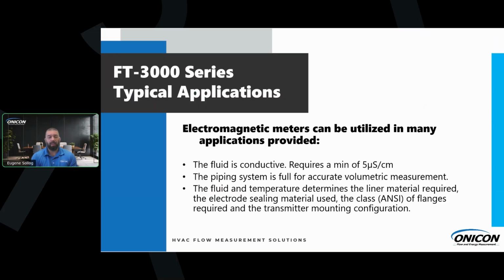We are measuring velocity and calculating the volumetric flow based on that velocity. Not only that, but if it's below one of the electrodes, the meter will go into an error and will not read properly. The fluid temperature and pressure is going to determine the liner and the flange size. So that's also a caveat to always look out for as well.